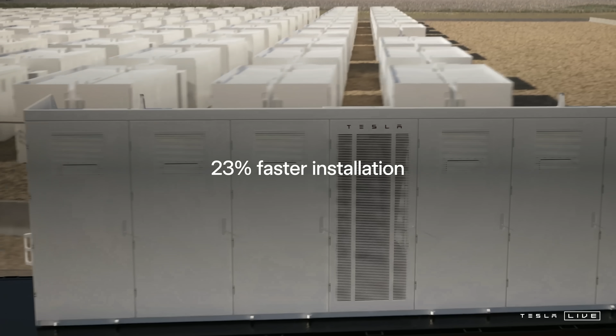Ship it to the field, ready to connect to the grid with zero on-site assembly. To that effect, Megapack 3 can be easily transported using a 7-axle trailer with no on-site assembly. With a higher energy rating, we have fewer Megapacks, reducing costs. And we went from up to 24 cable connections between the Megapack and the transformer down to 3 simple bus bar connections.